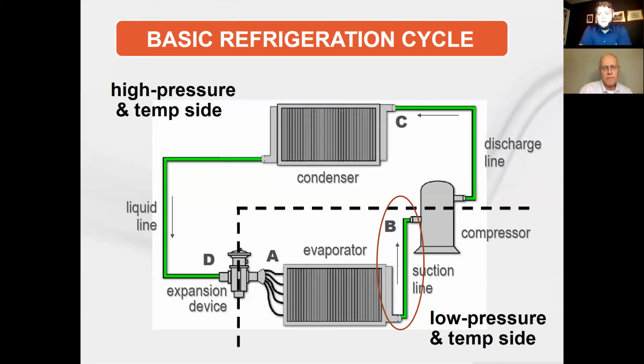Okay. For liquid to flow through that expansion device, there needs to be a pressure differential between D and A. If the pressure in D is the same as A, nothing's going to flow anywhere. So we need to boost the pressure in that liquid line enough to force liquid through from D to A. Yeah, I should have included the classic P-h diagram, but it tends to make people fall asleep.